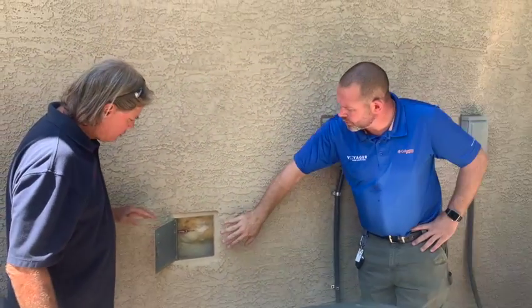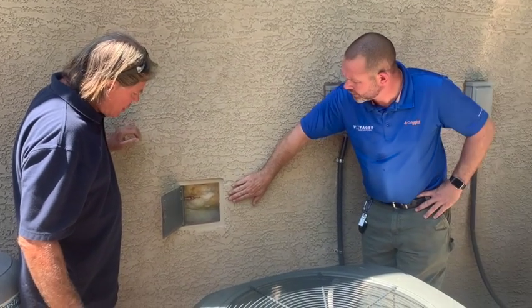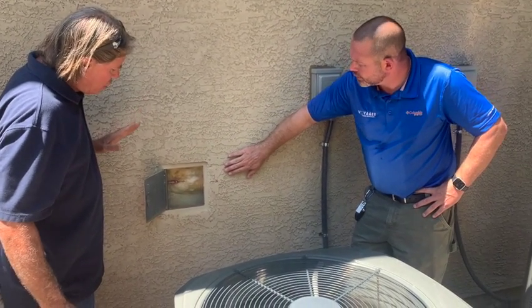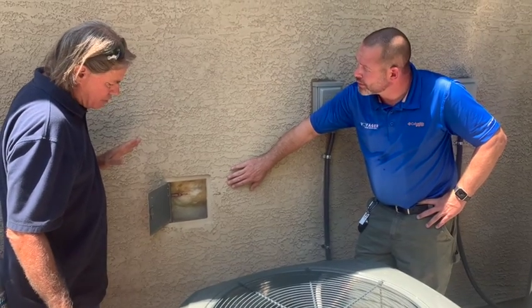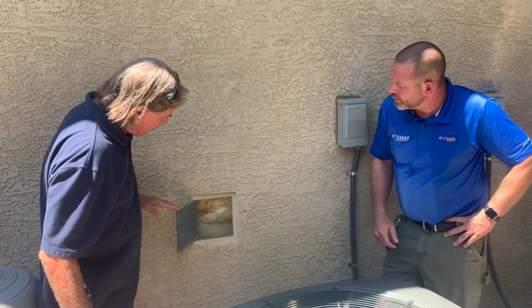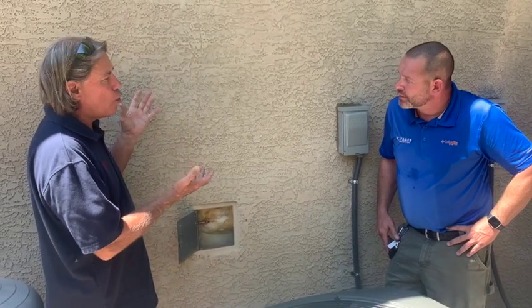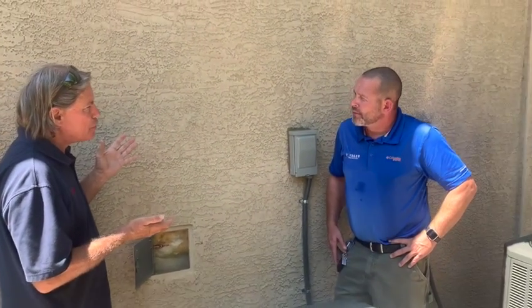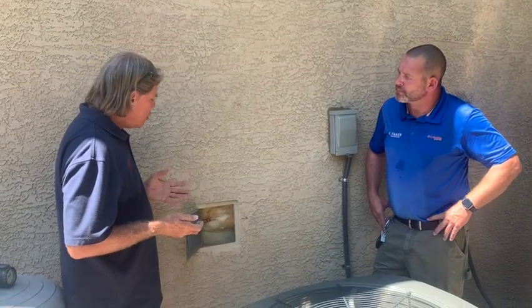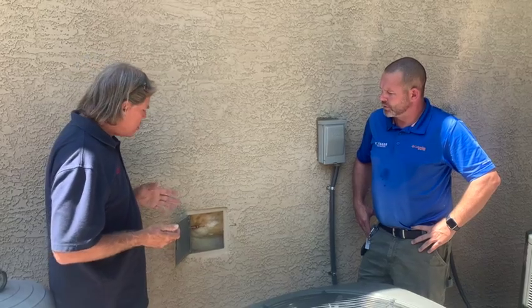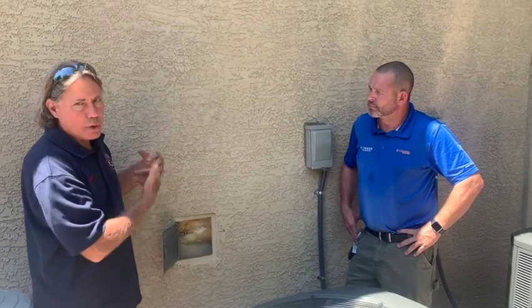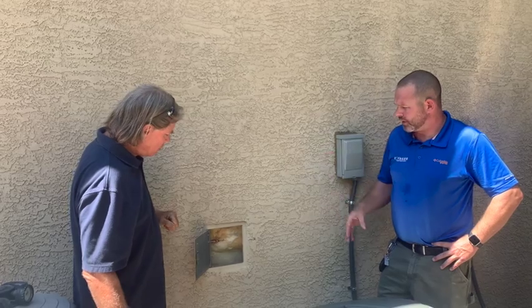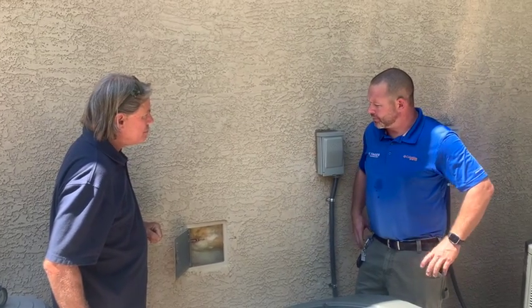And then, how long should we flow that for? You said twice a year? Twice a year is a good maintenance schedule. Once a year at least on a system that's working well. And for the length of flow, depending on the size of the home, if it's 2,000 to 3,000 square feet, for example, 30 seconds to a minute is good. If you've got a 4,000 to 8,000 square foot home, you want to flow it for a minute and a half, 2 minutes, something along those ranges. That way you have enough time for the whole system to flush. So nothing crazy, just enough to get that water moving and get some of that bacteria and all that out of there.